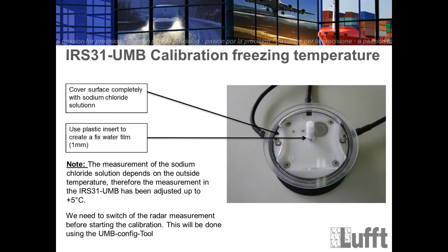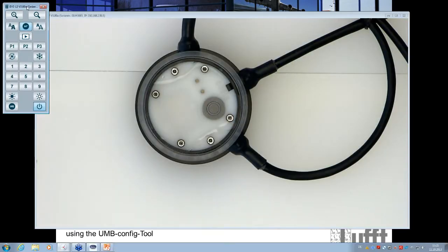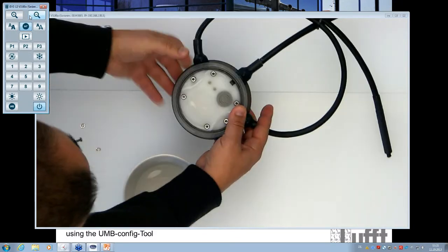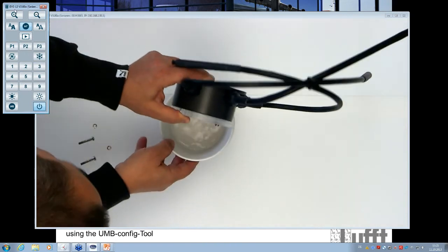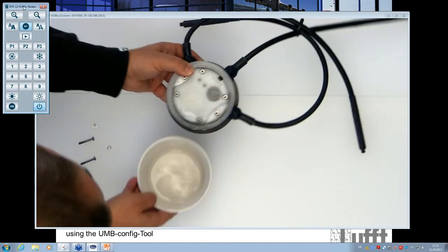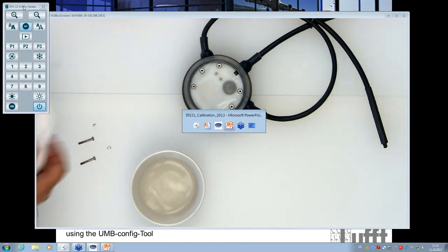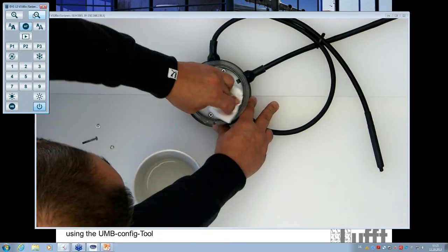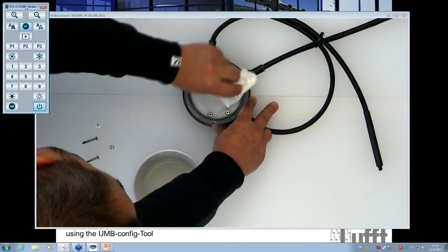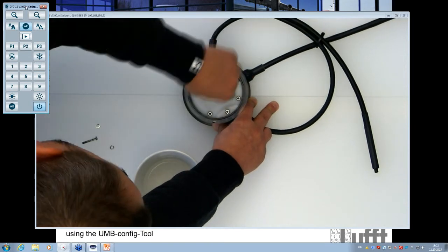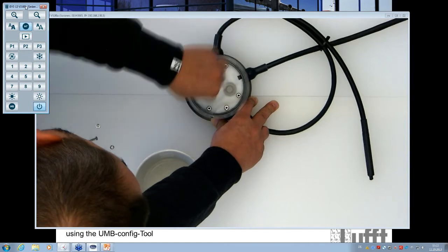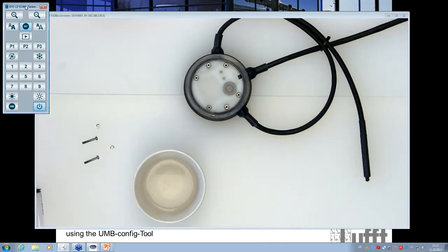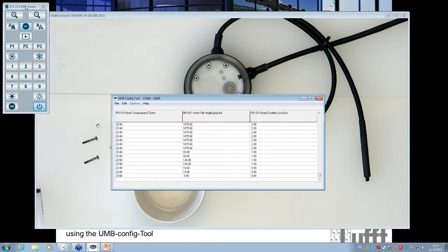The next step is the calibration of the freezing temperature. So I switch back to the camera now. The first thing we need to do is empty the water inside the plastic ring. That's easy for me here. You see that? I can do it like this. Of course, if you are in front of the station on the road, normally you can use a cloth, something like that, and you have to dry the surface like this, and then you can check again if the water film is now 0. That's the first thing we need to do after we have checked it. We have to go back to 0 now. Okay, now you see it's back to 0, it's dry now. Now we can start with the freezing point calibration.